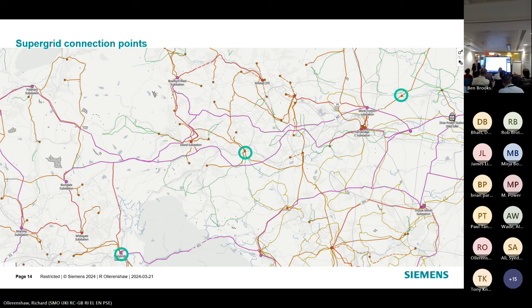The upshot is, we've got so much choice of good connection points if we can use those 132 kV supplies that the way in which we design the electrification system changes. When before it was about where can you take the power, and you can see on that previous map how few places were practical, and then the natural implication being how big do you need to build your overhead line to push that power all the way along to the midpoint until you can get to the next supply area. It changes. It becomes actually what's most operable, maintainable railway.